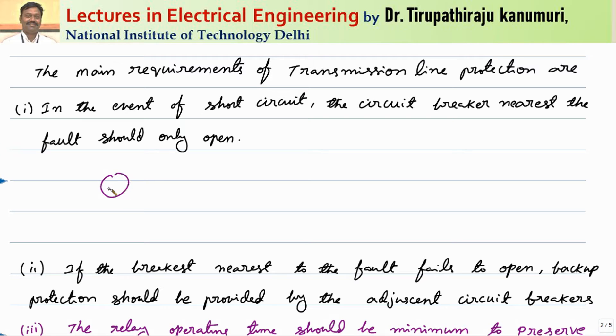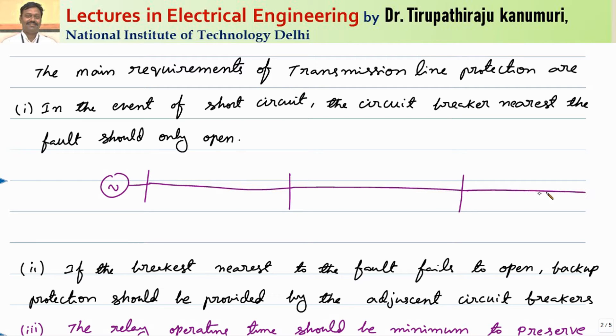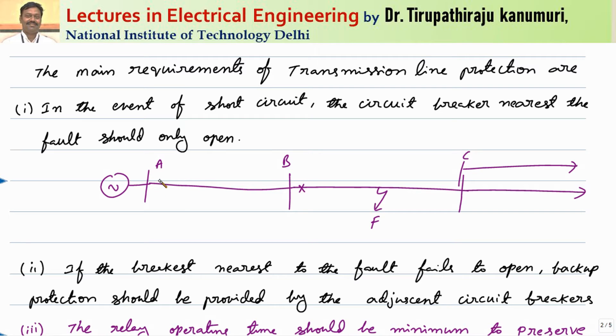Let us take a singly fed system — there is an alternator or generating station. There may be some parallel feeders at some places, represented by points A, B, C. Let us assume a fault has happened at a point. Whenever the fault happens, I want my circuit breaker at point B to operate first, so that the other part of the system is not disconnected and the stability of the system is not affected.